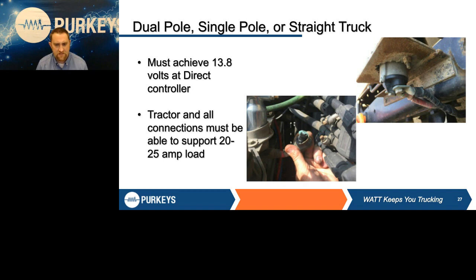But if you look at the examples here, that dual pole receptacle, in what I've experienced, is pretty vulnerable where it's mounted. Typically you'll see it corrode right at the connection point where the cable connects to the receptacle. As you can see in the picture there, I just barely touched the cable and it came off. So you really want to inspect that connection point. You really don't want to see any kind of tape wrapped around the connection; you want that dual wall adhesive lined heat shrink to really seal that connection.